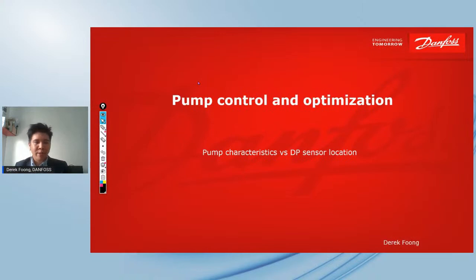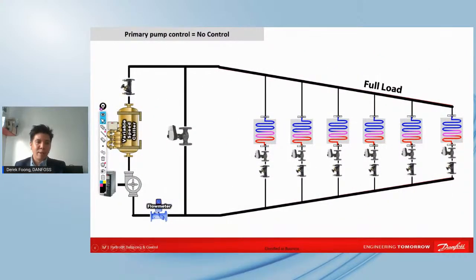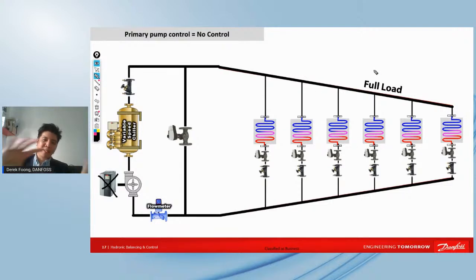All right. So now you have an idea of the affinity law, how it works, and some of the pump control dynamics. But how about if we look at it in a way that we put it in a system, and let's say this is the hydronic system where we have a variable primary system. We'll go a little bit deeper into that later. And in variable flow systems, if we do not have a variable speed drive, all right, so what will happen? Now this is full load, and we call this the hydronic ladder. You can see that this ladder is horizontal, right? And you have fan coils and air handlers along the line in parallel. And then you have two-way control valves and manual balancing valves.